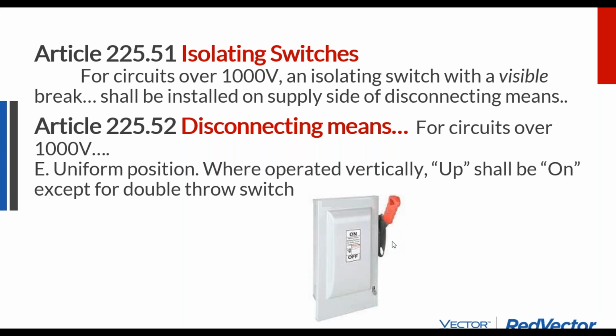And then once you get over 1,000 volts, they say up indicates on, unless it's a 3-way switch where the middle position is off, but up is always going to be on. Up is always going to be the grid side of things. Up is going to be energized, where down or the middle position is off.